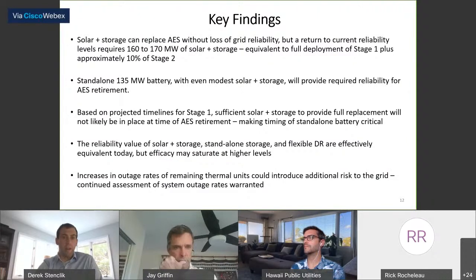So I'll summarize with a couple of different summaries here. First, key findings, then some plans about the period of transition the grid is going through. First key finding: solar plus storage can replace AES without a loss of grid reliability, but a return to current reliability levels requires 160 to 170 megawatts of solar plus storage. That's equivalent to a full deployment of the stage one projects and approximately 10% of the stage two projects. So there's certainly a timing concern with solar plus storage alone, because not even all of stage one is scheduled to be in place before AES retires.